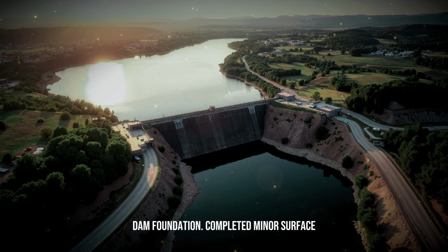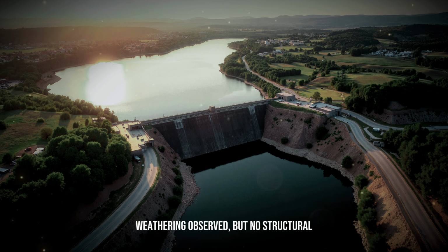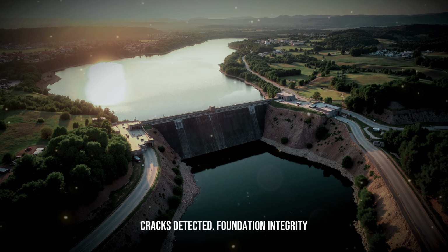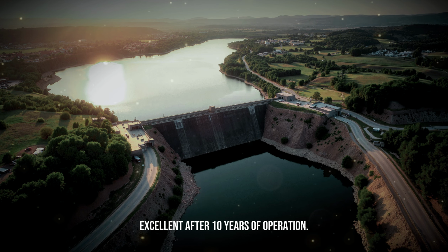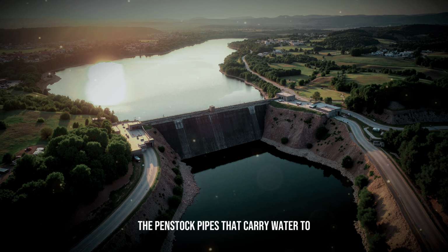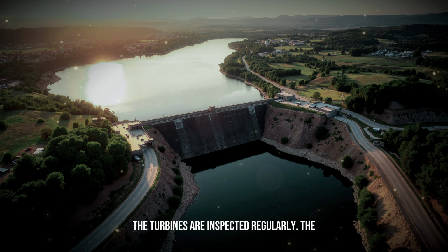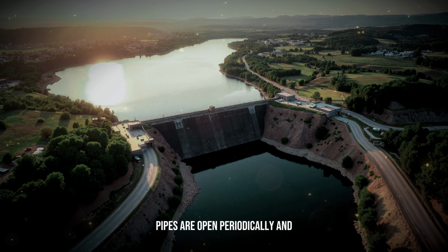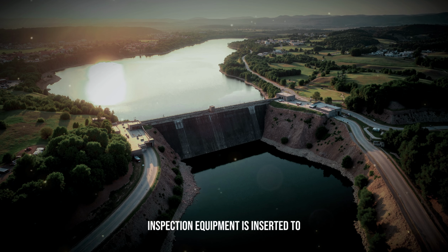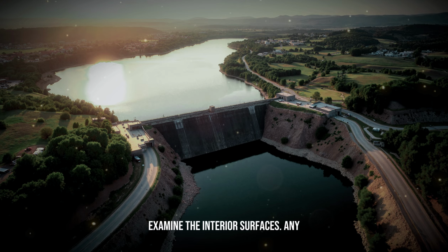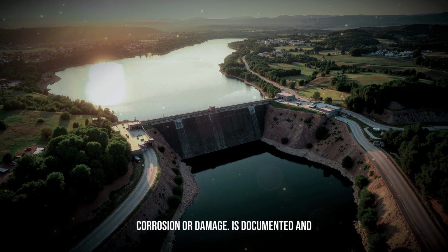Underwater inspection of dam foundation completed. Minor surface weathering observed but no structural cracks detected. Foundation integrity excellent after 10 years of operation. The penstock pipes that carry water to the turbines are inspected regularly. The pipes are opened periodically, and inspection equipment is inserted to examine the interior surfaces. Any corrosion or damage is documented and repaired.